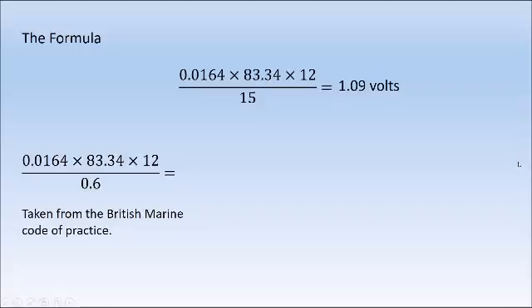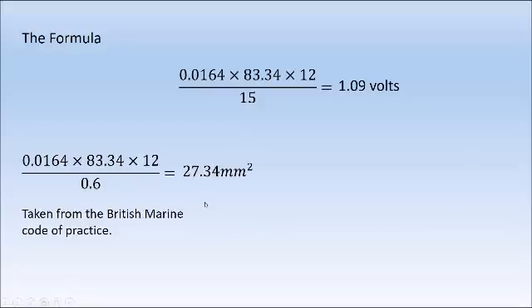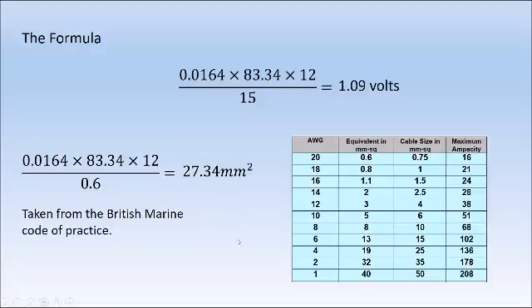1.09 volts is way above the 0.6 volts allowed for this circuit. So the next step is to go back to the previous approach and actually calculate the correct cable size. Using the similar formula — 0.0164 times 83.34 times 12 — but this time dividing by our maximum allowed volt drop (0.6V) instead of the cable size, we get 27.34 millimeters squared. Again, this is an odd size that manufacturers probably won't make, so we go to the cable chart: 25mm² is too small, so 35 millimeters squared is perfect — that will maintain our 0.6-volt maximum allowed volt drop.